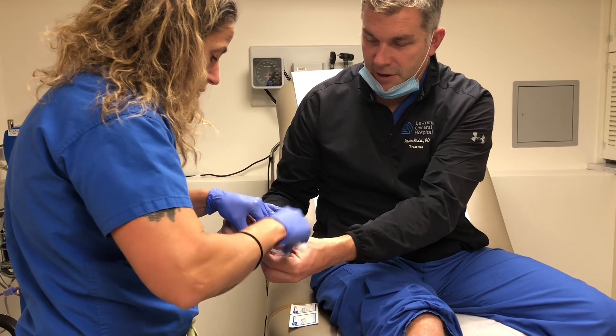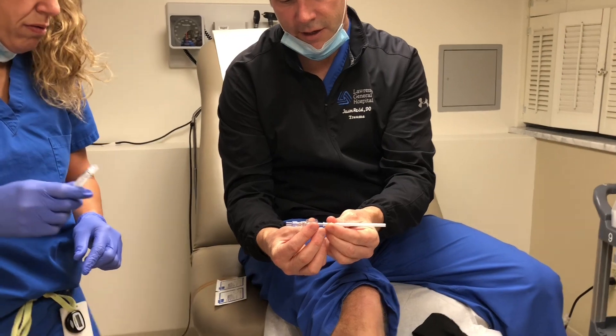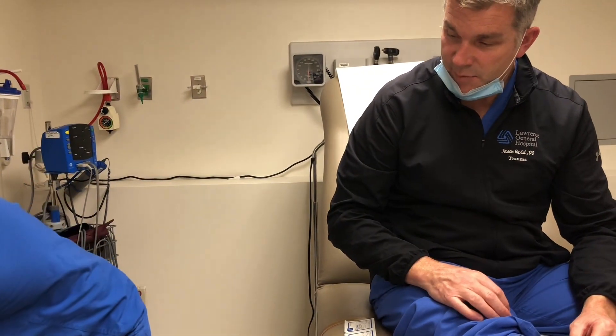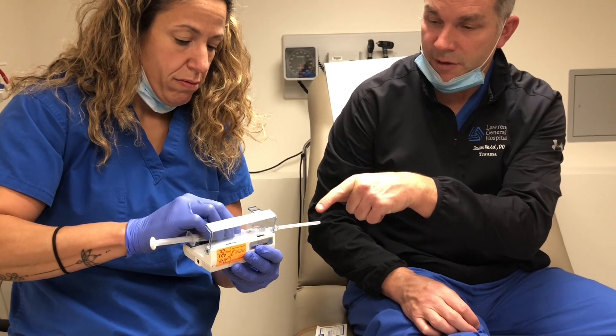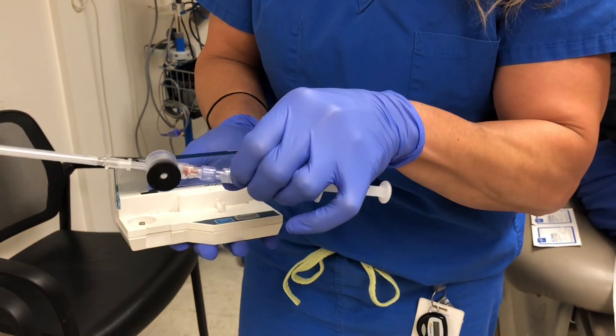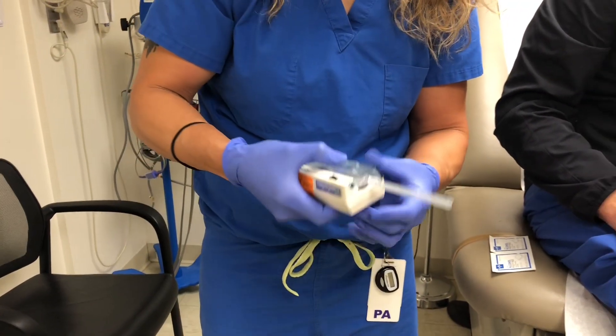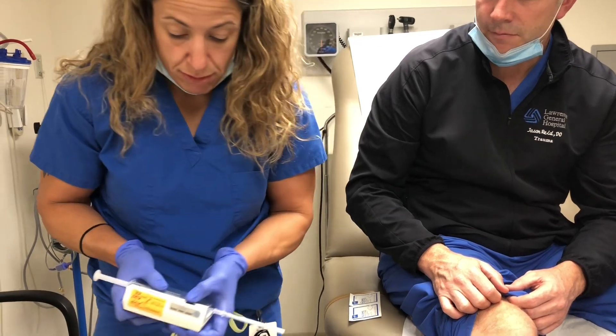The needle can only fit on one end, and likewise the syringe can only go on one end. Once assembled, you open your pressure monitor and depress the rubber gasket onto the mount — there's a black rubber gasket on the bottom that just sits right in. Press it down; it clicks and pops in. Then you can close it and turn it on.